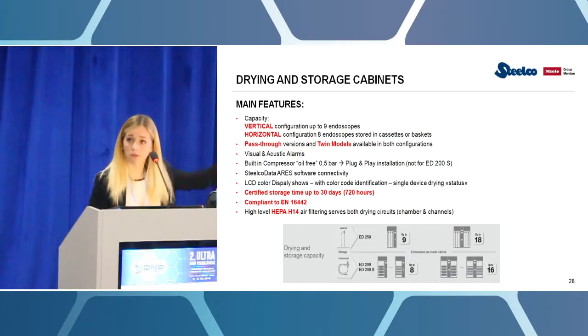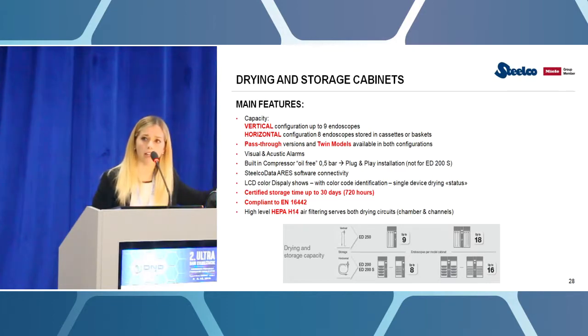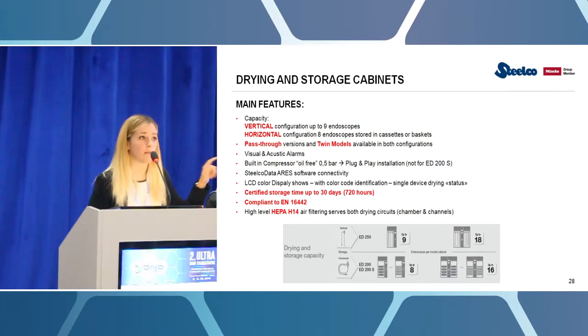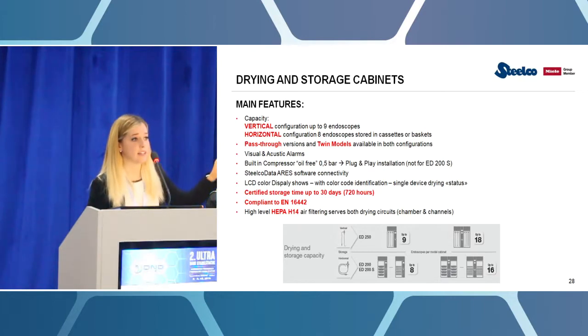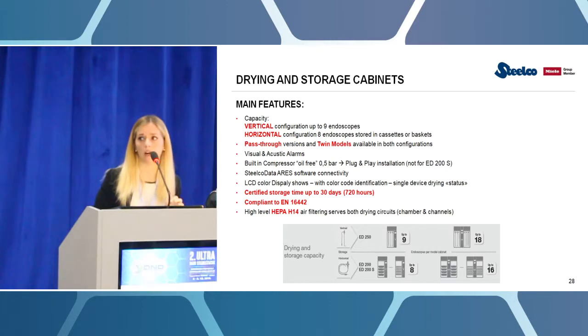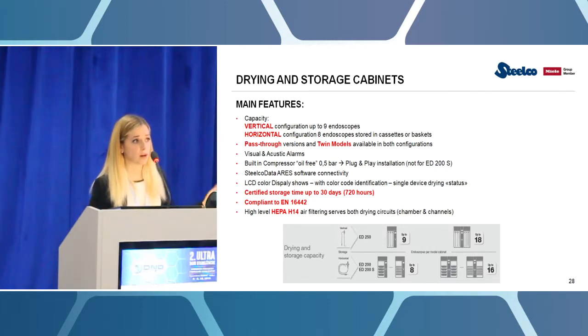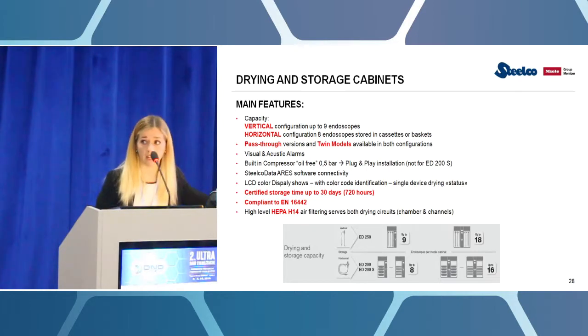The very nice feature of all these cabinets is the fact that they have been certified from an independent laboratory to maintain the aseptic conditions inside the channels for 720 hours. This means 30 days. So once you put an endoscope inside that cabinet, it's been certified that it can stay there up to 30 days. Then you need to reprocess it.